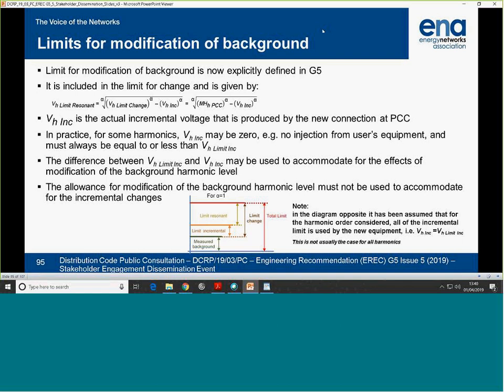And the reason for that is that the limit change is calculated locally at the PCC. It does not include the effect on the remote node. So the level that is given for the PCC cannot be used to inject more from it, because you don't know what happens at the remote. For emission, only the incremental limit has to be considered and used.